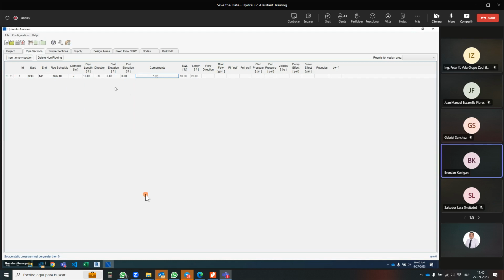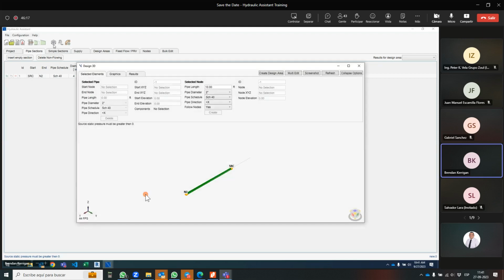So you're asking about a standpipe calc. I'll do a real simple one here for us, and I'll tie this into the design 3D option. You can just come in and create a bunch of pipe sections here by hand. If you've got a simple item, you can open up the 3D viewer. It's going to give you our one pipe section here. So if we want to just create a very simple standpipe, and I didn't really cover this, but you can click on items within the 3D viewer. When I click on a pipe, it gets highlighted in yellow. Its details get filled in here. So if I want to change the length, I can change it down to 5 feet, change it up to 10 feet, and so forth. If you want to create a new pipe in the viewer, you can click on a node, it gets highlighted in yellow. You can choose what you want to create, hit that create button, and it's going to start creating the pipe nodes for you.